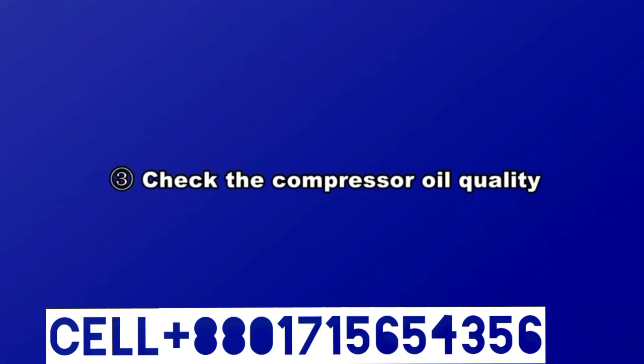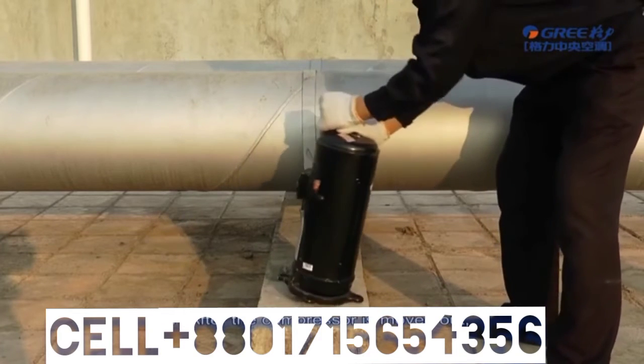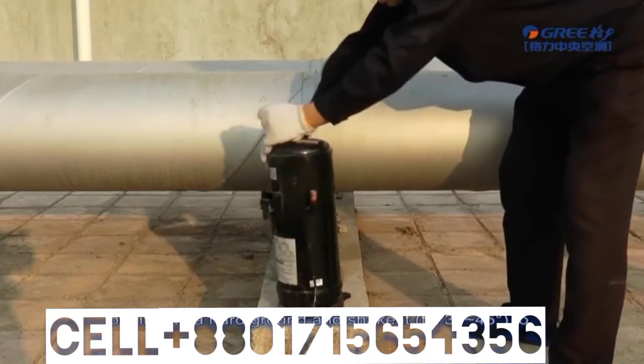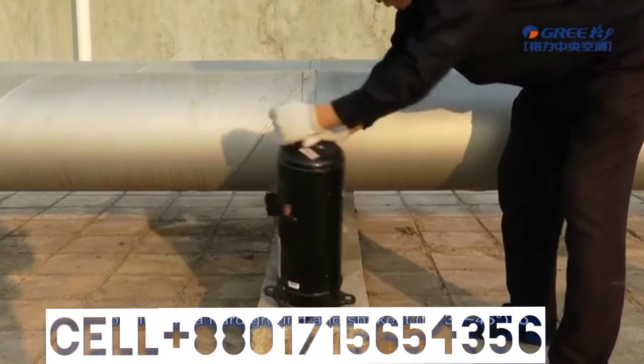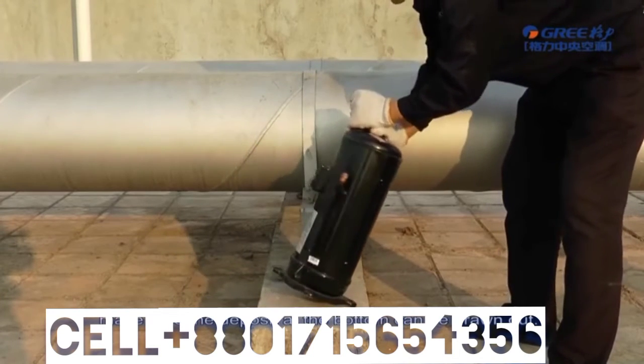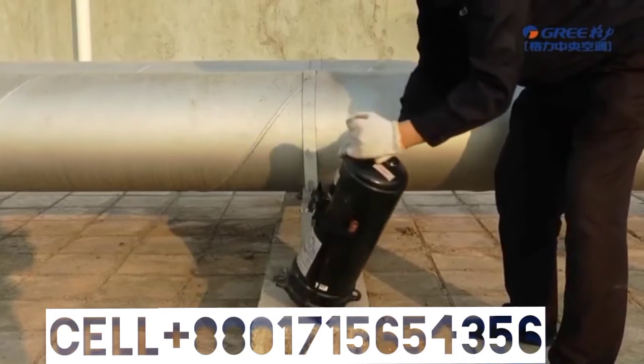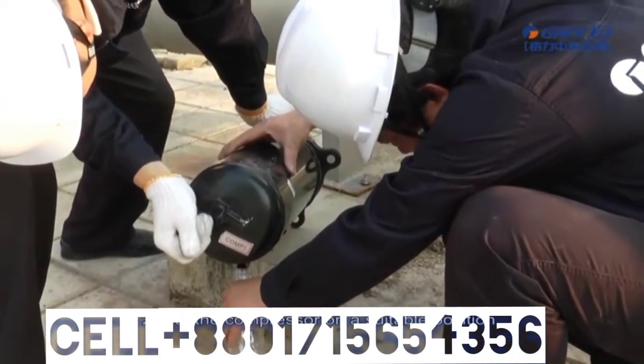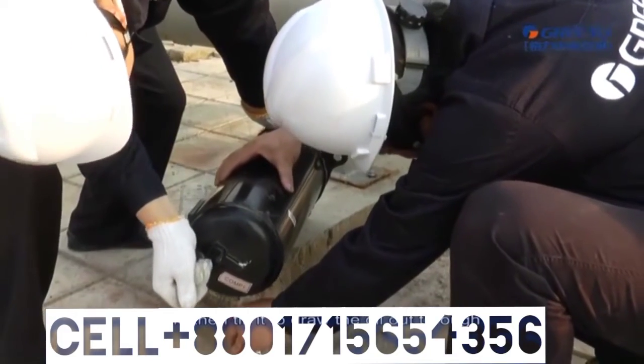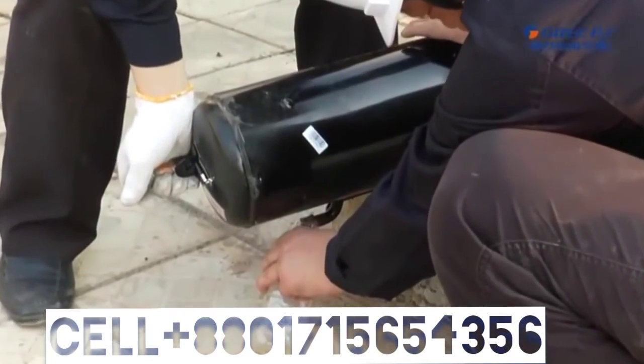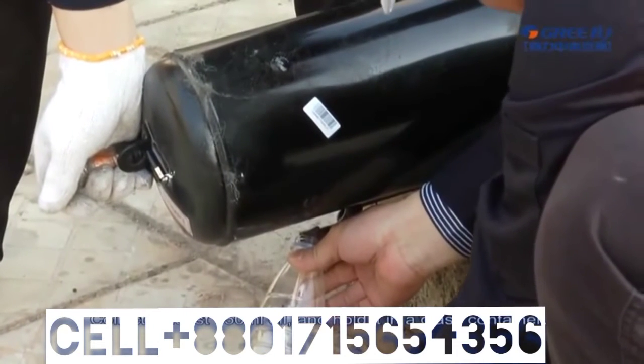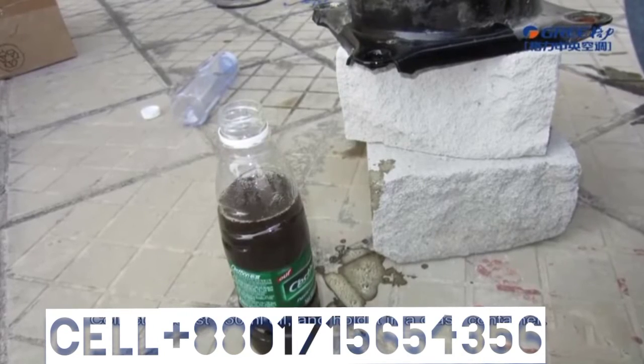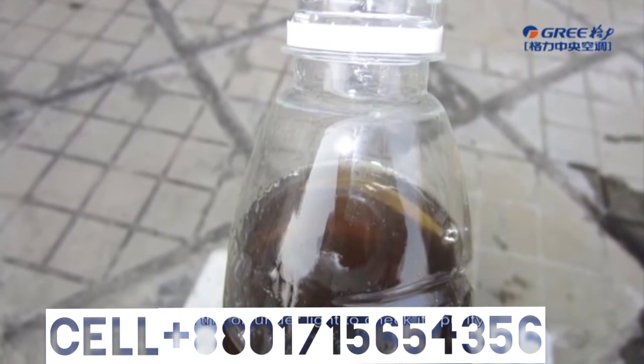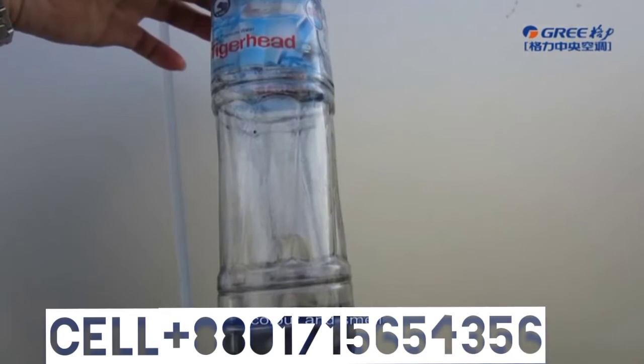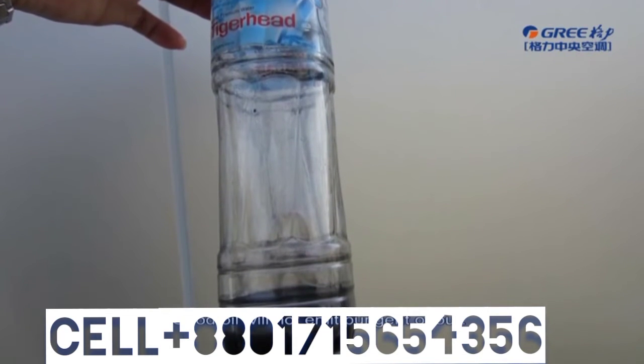Step 3. Check the compressor oil quality. First, after the compressor is moved out, put it onto a hard ground and shake it. Tilt 30 to 45 degrees to make sure the deposit at the bottom can be drawn out. 2. Put the compressor on a suitable position and then tilt it to draw the oil out through the vent of the compressor. Collect at least 150 milliliters of oil and hold it in a glass container. Put the oil under light to check its purity, color, and smell. Good oil will not emit pungent odor.